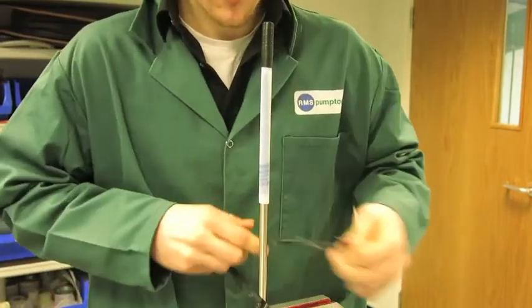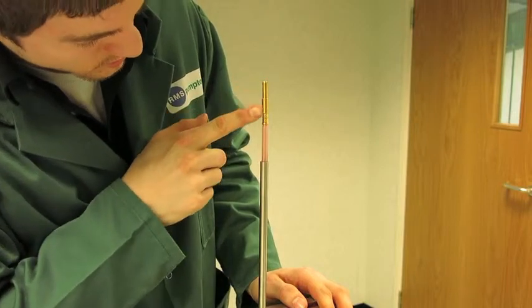When instructed to remove the phase end protection, you should always check for moisture ingress and contamination on the PFA insulation and gold contact pin.